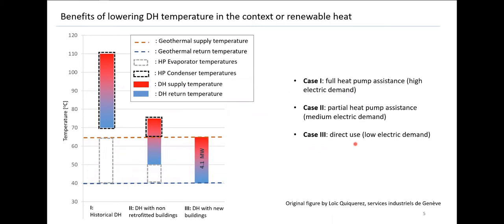Depending on the temperature level of the district heating, we have very different levels of required heat pump assistance to use this geothermal heat source. In the first case — a not very good situation — if we need a supply temperature of 110 degrees and a return temperature of 70 degrees, we need full heat pump assistance, since the return temperature of the district heating is above the temperature of the geothermal resource. In the second case, with a supply temperature of 75 degrees, we need only a temperature lift of 10 degrees, so we have partial heat pump assistance and use much less electricity.